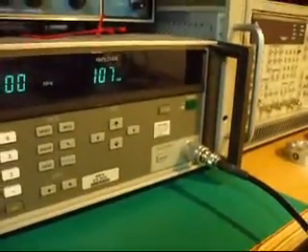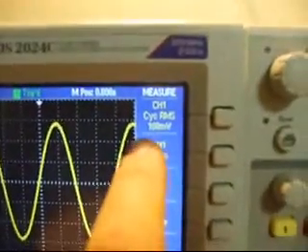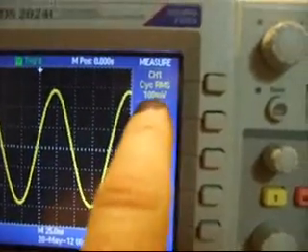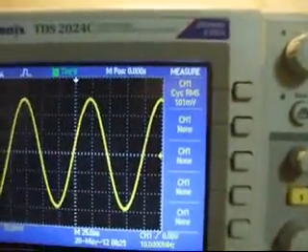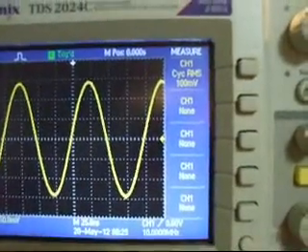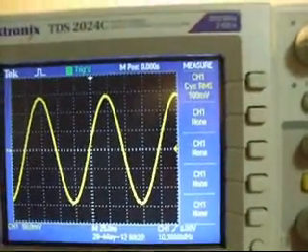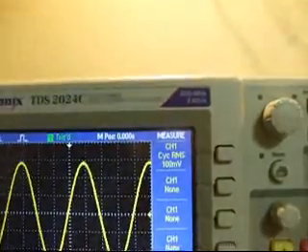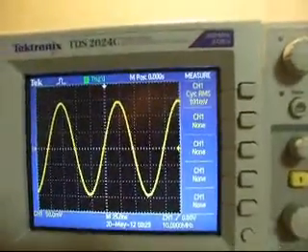Again, the signal generator like the one I was playing with earlier expects a 50 ohm load. And since the scope doesn't have an attenuator in it with a 50 ohm load, it's a 1 megaohm. And I have to put a 50 ohm load on it, which is from Tektronix. So what I'm looking for is my RMS value up here, which is 101 right now, 100, varying a little bit. I want to see that it stays above 70.7 millivolts out to the specified bandwidth of 200 megahertz. And anything beyond that is just kind of bonus bandwidth.